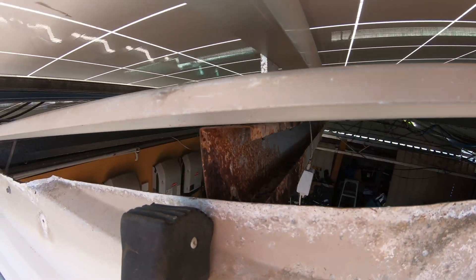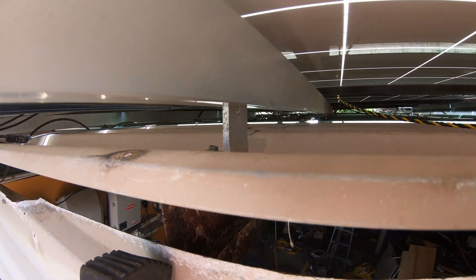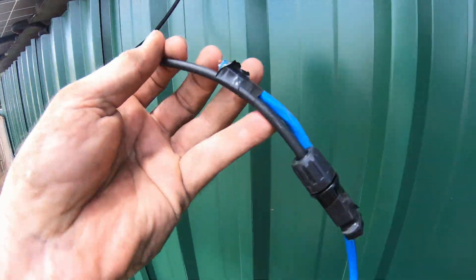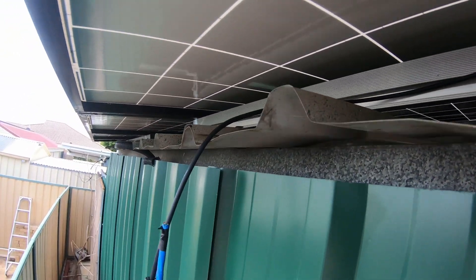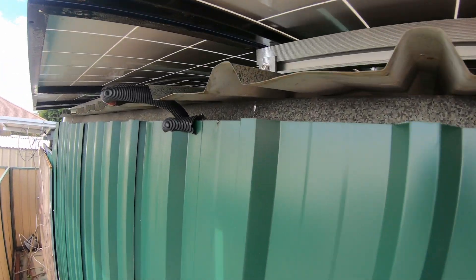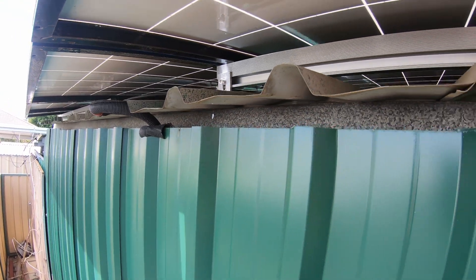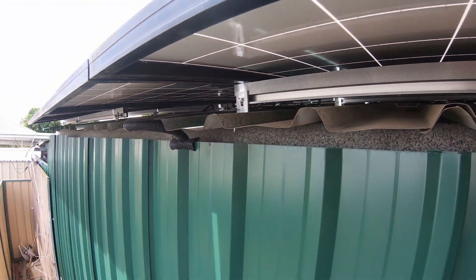This is not going as smoothly as I'd like. I have to whip the ladder around the other side and drag that cable down — what a pain. I really need one of those nylon joining strips to make it a whole lot easier. Through to the other side — that was a nightmare. Up there is where I had the rub-through, and you can actually see where it arced. The piece of conduit that was there before fell off and that's what caused the rub-through.